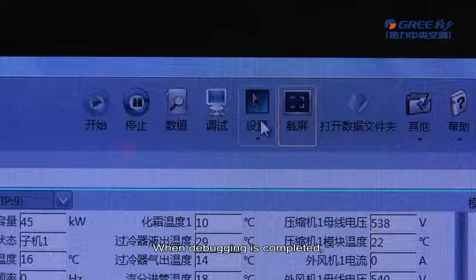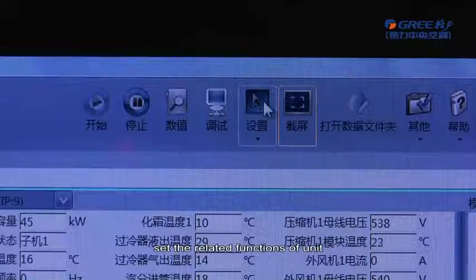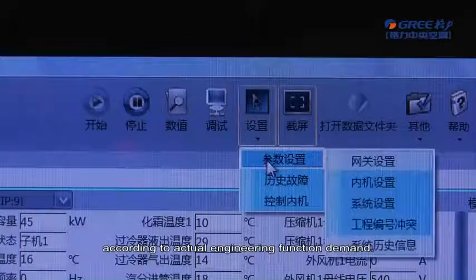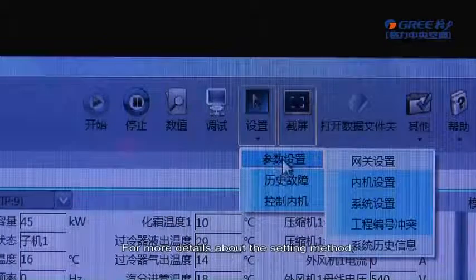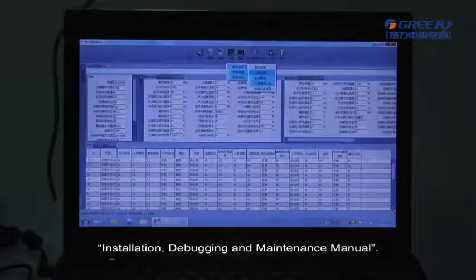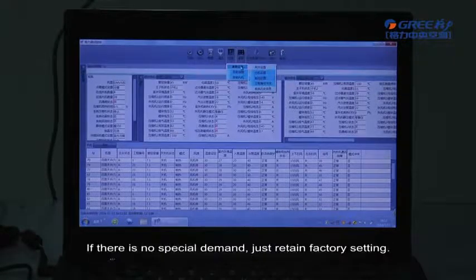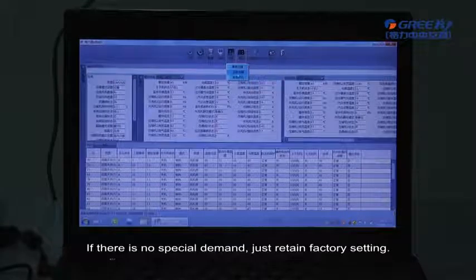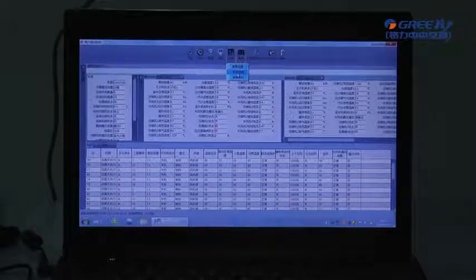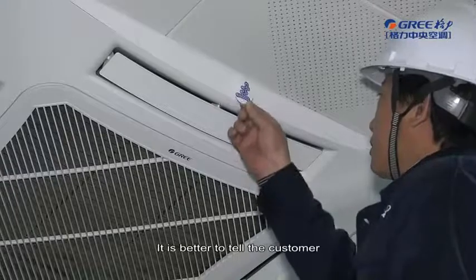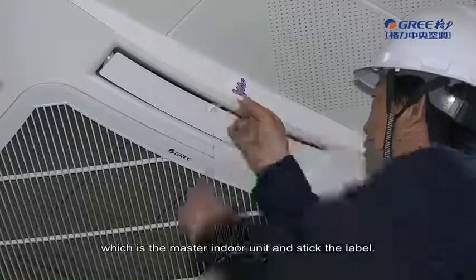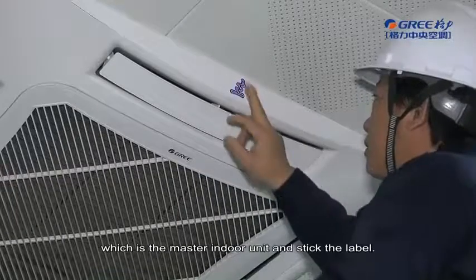Engineering function setting. When debugging is completed, set the related functions of unit according to actual engineering function demand. For more details about the setting method, please read the Installation, Debugging and Maintenance Manual. If there is no special demand, just retain factory setting. It is better to tell the customer which is the master indoor unit and stick the label.